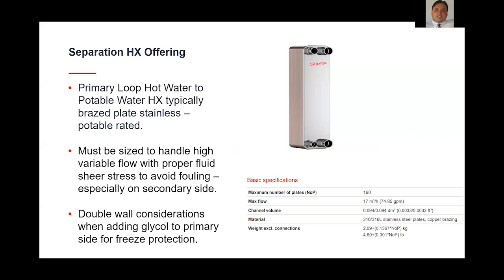It's important that these are sized correctly, and you have to pay fairly close attention to this because, again, you're dealing with very low charge rates on the primary side with a high degree of water flow turn down depending on loading. So near the end of tank charge, you could see your higher flow rates near the maximum. And then under extreme cold ambient conditions, you could see flow rates that are possibly 1/10 of those maximum flows that can be experienced. So you have to be careful with brazed plate heat exchanger selection.